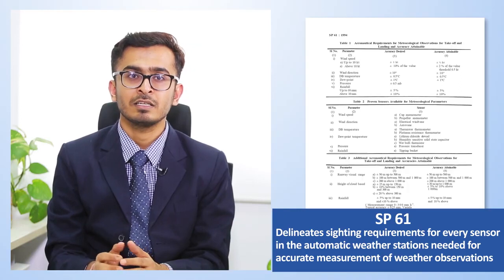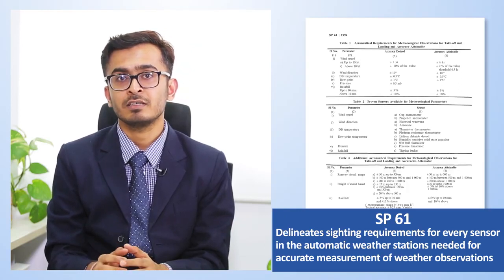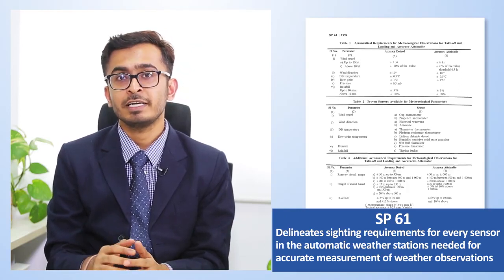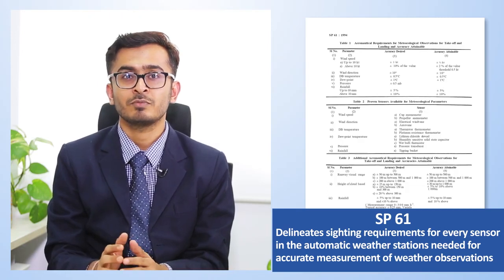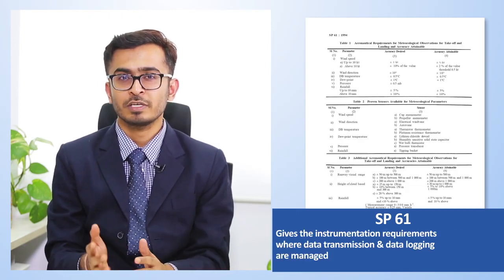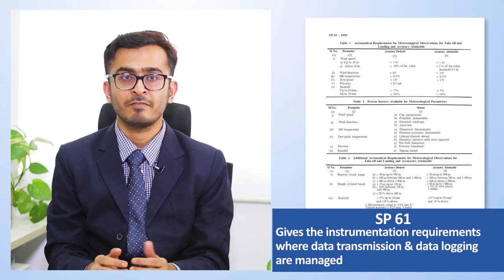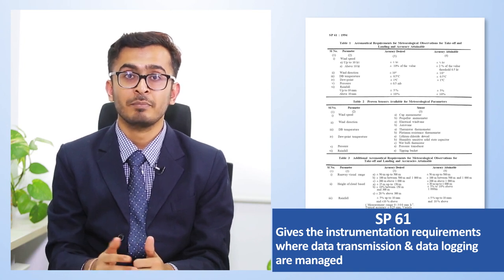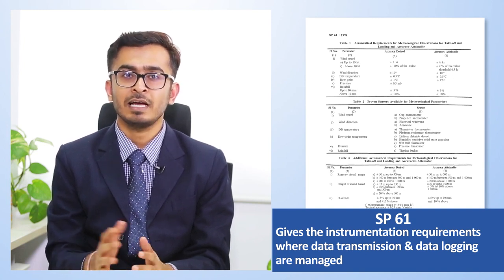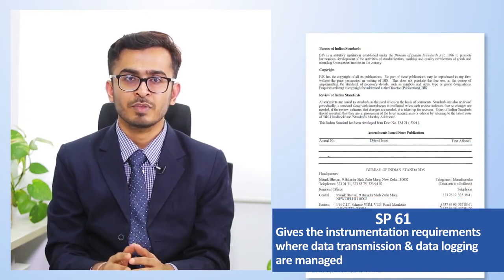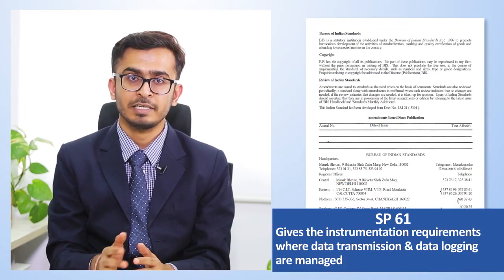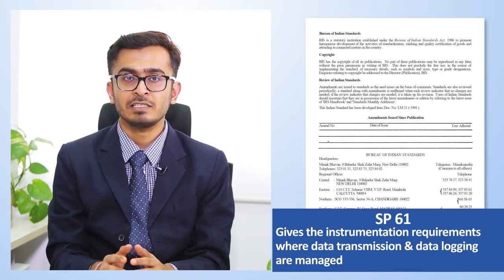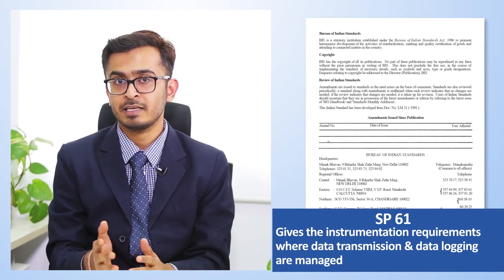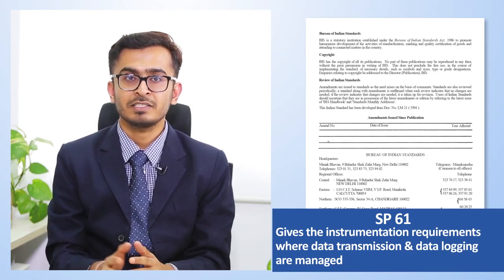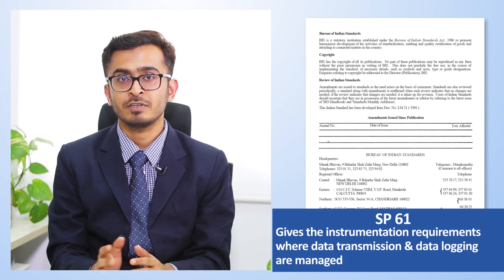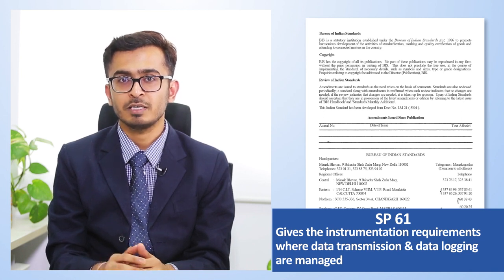It also delineates the siting requirements for every sensor in the automatic weather stations, which are needed for accurate measurement of the weather observations. It also gives the instrumentation requirements where data transmission and data logging are managed. These requirements are in line with the international recommendations by the World Meteorological Organization, that is WMO, and the International Civil Aviation Organization, that is ICAO. It clearly mentions the frequency of calibration, which refers to the calibration standards as per WMO recommendations.